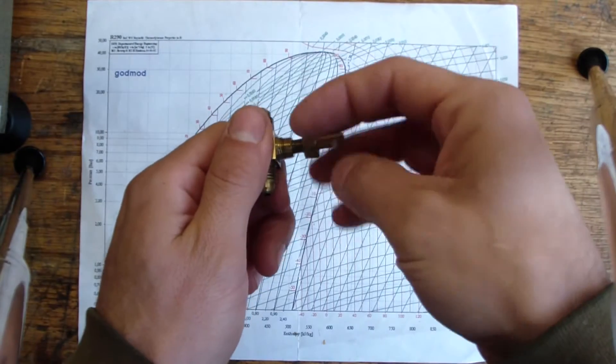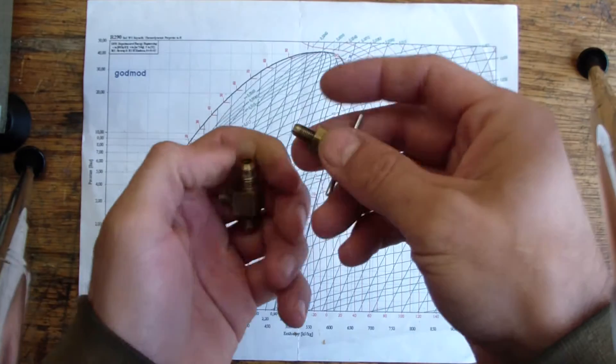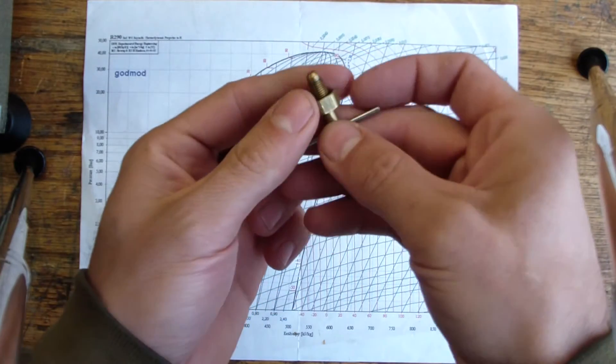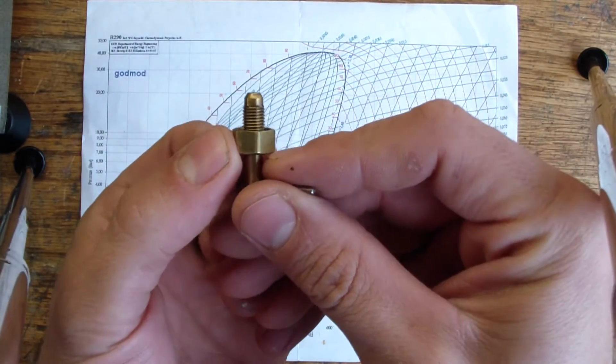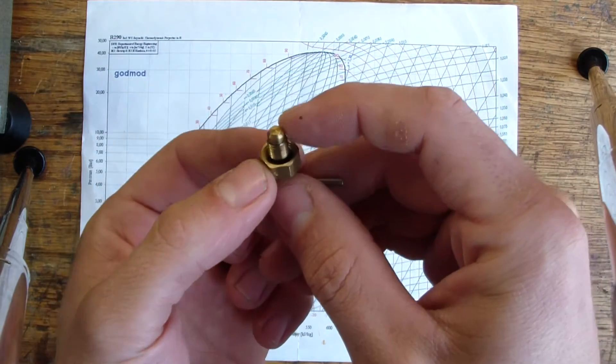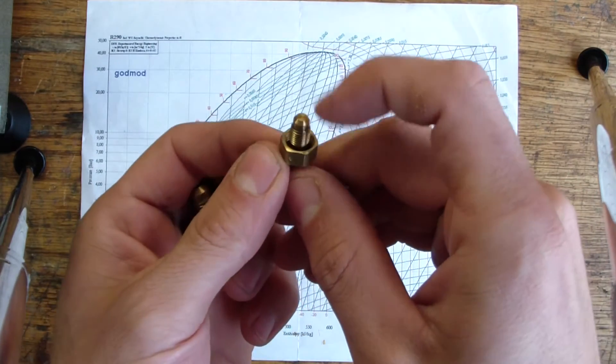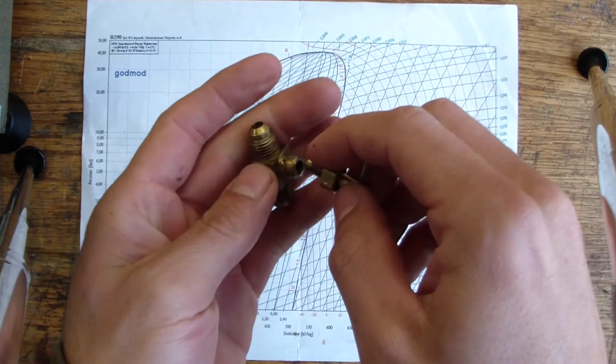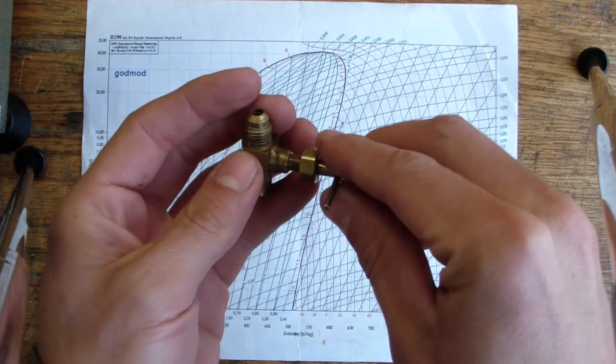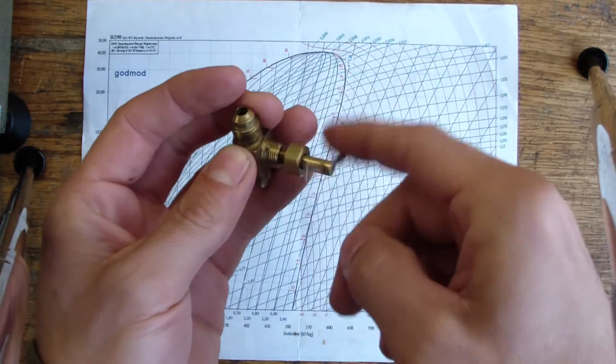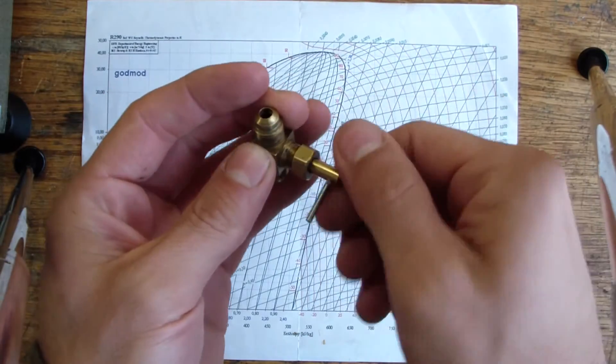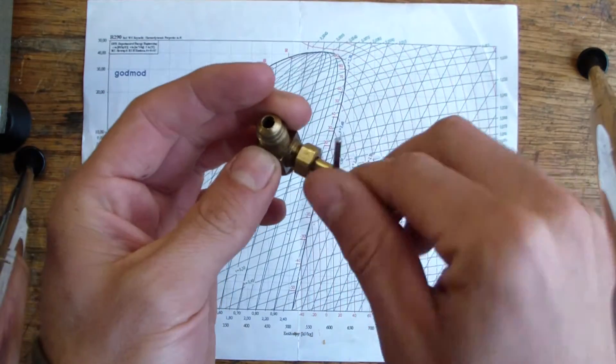And I'm just going to back the whole needle assembly out of the valve body. See, it's called a needle valve, but it's kind of a misnomer because you can see it's got a very wide taper on it, and it's got a very blunt end to it.